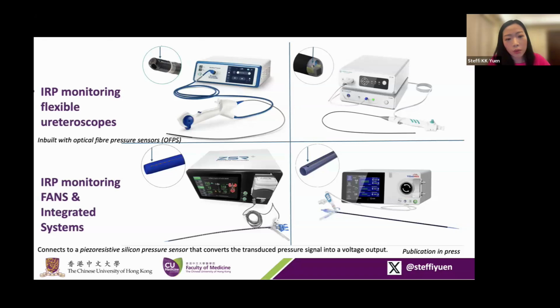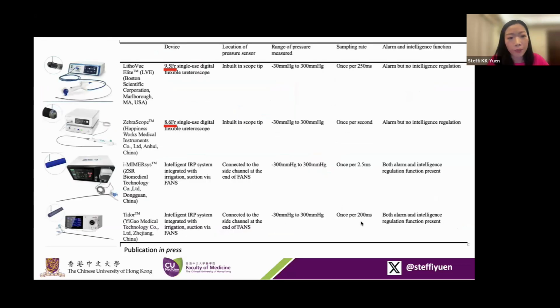As for the lower two images, you can see the IRP monitoring sheaths with different sheath designs. You can see on the left side, the ZSR MIMER system has multiple holes that are connected to a tiny channel that's inbuilt into the sheath's access sheath. Whereas another brand shows another tiny channel with a single hole that transduces to the sensor, which is connected to the system. It's connected to a piezoresistive silicon pressure sensor that converts the transduced pressure signal into a voltage output that's output on the interface.